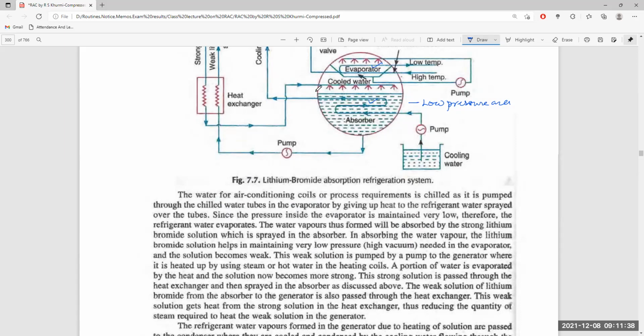I am going to explain you afterward. This is sprayed here, and the high temperature water is sent to the evaporator and is cooled by this stream of cold water sprayed over the tubes carrying the refrigerated water. Since pressure inside the evaporator is maintained very low, the refrigerant water is evaporated. The vapor will be absorbed by the strong lithium bromide solution sprayed in the absorber. In absorbing the water vapor, the lithium bromide salt helps in maintaining the very low pressure, high vacuum needed in the evaporator, and the solution becomes very weak.